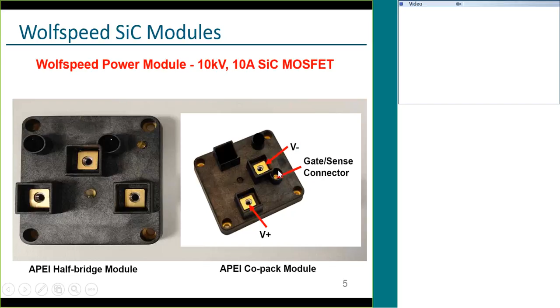So let me jump into the gate driver design and qualification. Our motivation is to drive these devices at medium voltage. We need a gate driver, and the most important thing is to achieve a very high isolation voltage. The challenge is making a gate driver that can withstand 10 to 15 kV isolation while switching at 10 to 20 kilohertz, with the high dV/dt required from these silicon carbide devices to achieve low loss.